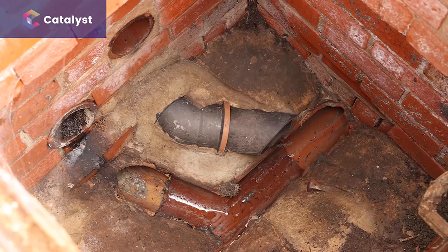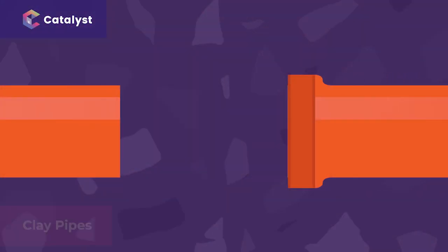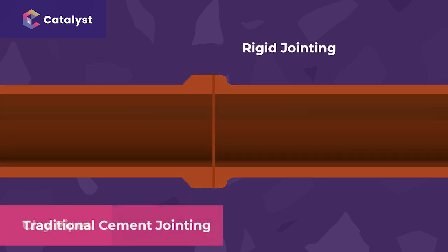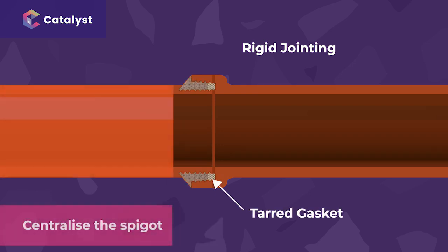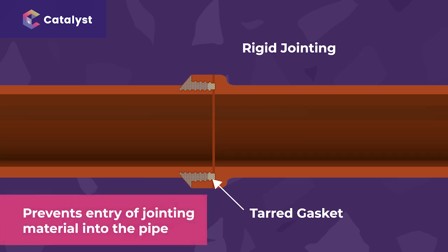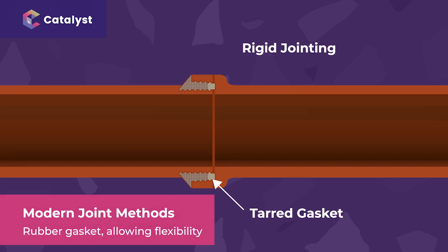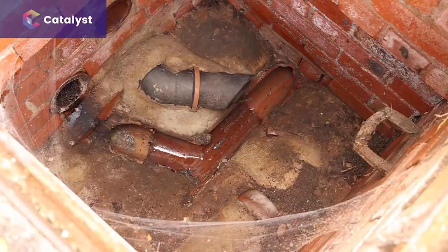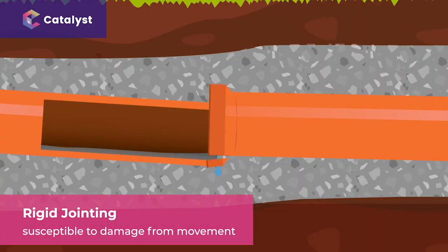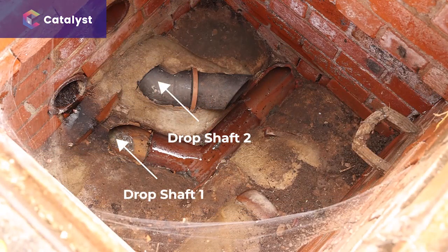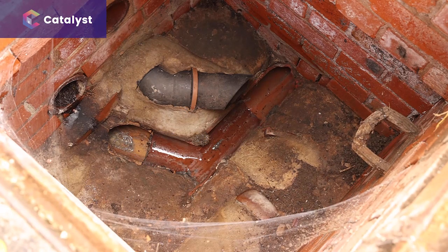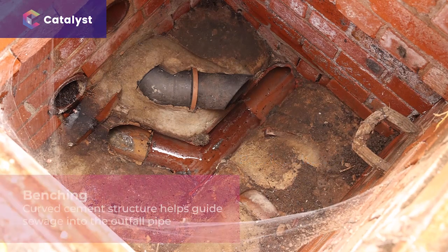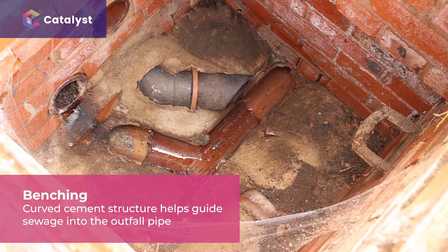A CCTV investigation is carried out to assess the pipe condition. On this site we have clay pipes with a rigid jointing method of installation. Traditional cement jointing used a tarred gasket to centralise the spigot in the socket and prevent entry of jointing material into the pipe. More modern jointing methods allow a rubber gasket to provide some flexibility in clay pipework. The rigid jointing was susceptible to damage from movement. The manhole has two backdrop shafts entering it, consistent with the drainage engineer's initial assessment. One drop shaft appears to have been repaired at some point as it has a plastic pipe coming over the top of the benching — the curved cement structure that helps guide sewage into the outfall pipe.